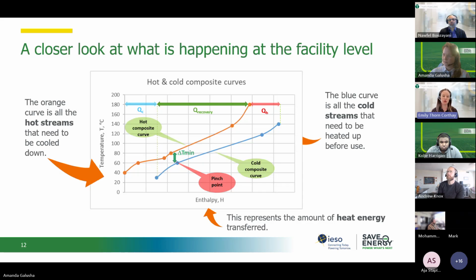Instead of using a separate cold utility, such as cold water from the cooling towers for the hot stream, and a hot utility like the boilers and steam for the chemicals, we can design a heat exchanger where the chemicals tank is heated using an indirect heat exchanger with the flue gas. This results in less steam, meaning less hot utility used, and less cooling water, leading to big energy savings. That's just one example, but with the software, you'd optimize all the heat exchangers one after the other, holistically and together.